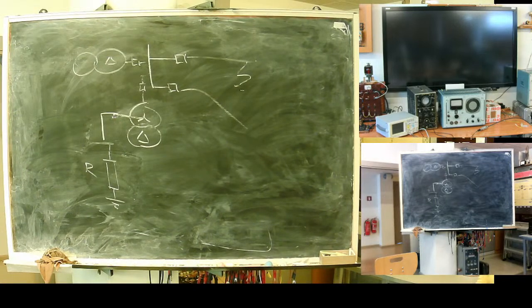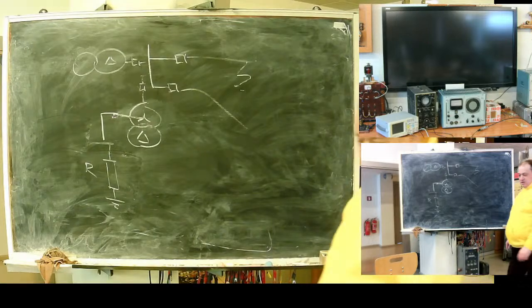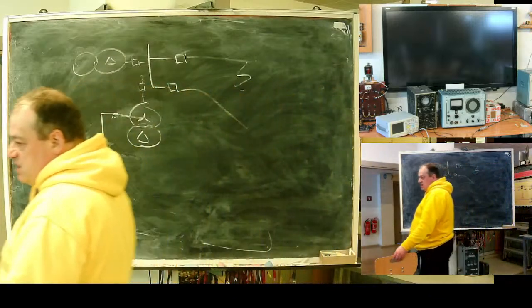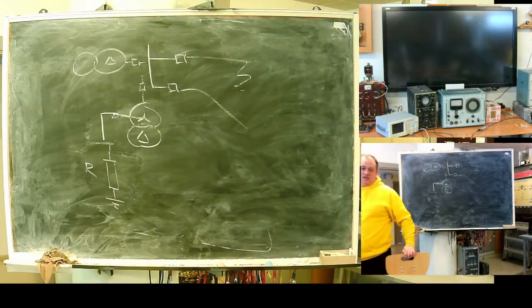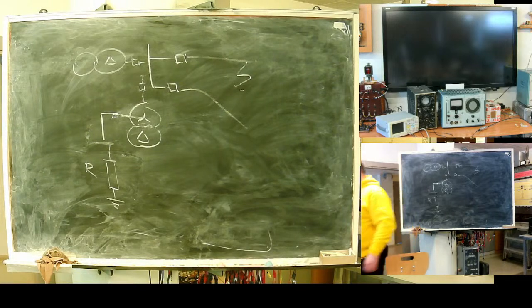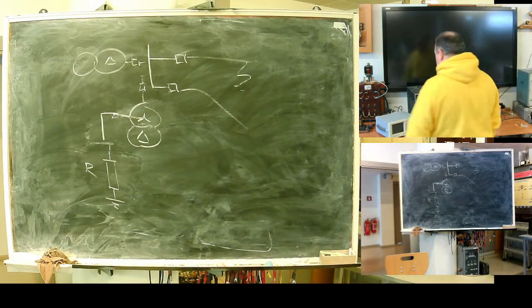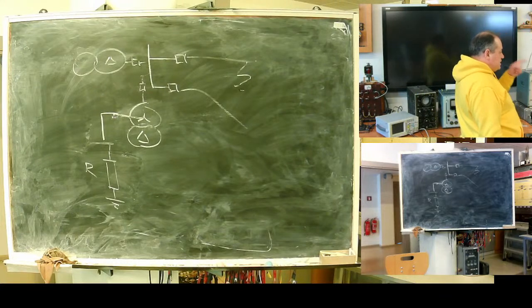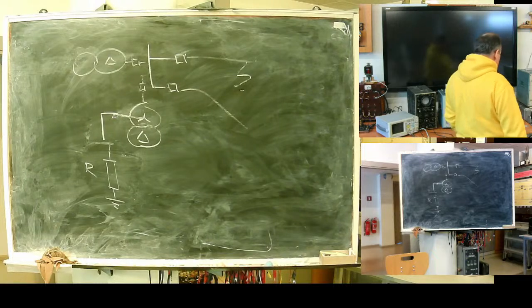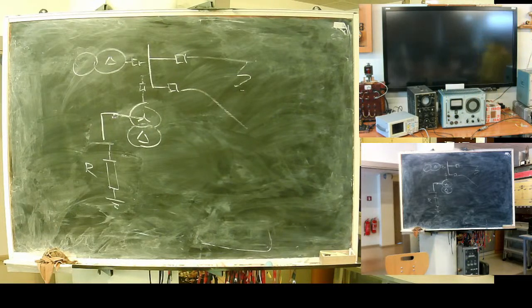These resistors reduce the equivalent quality of the resonant contour. They protect against resonant faults and during transients. One more thing, on a voltage transformer, this open triangle winding also should be loaded with resistance to prevent resonant transients. This version is cheaper and can be used, but only in relatively small networks.